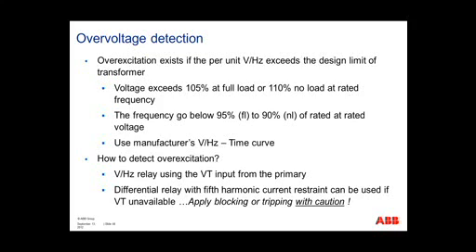There's two ways to actually detect overexcitation. You can use an input from the VT, the metering VT on the high side of the transformer. If you do not have a VT connection, you can calculate it using fifth harmonic current restraint measured from the relay. There is a note that says apply blocking or tripping with caution, because if you're in an overvoltage or overexcitation condition, typically you're in the hottest of days, coldest of nights, and you're having a strong load on your low side. So if you trip, you're going to put a lot of people out in the dark. If you block and you don't trip, you could possibly overload the transformer.